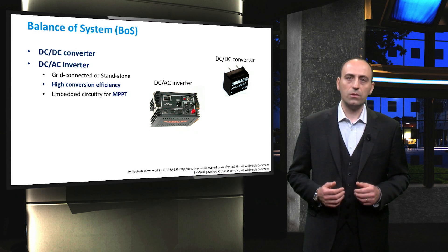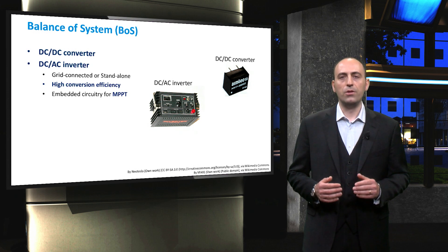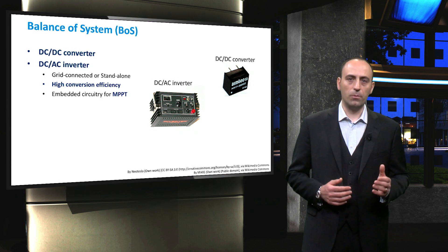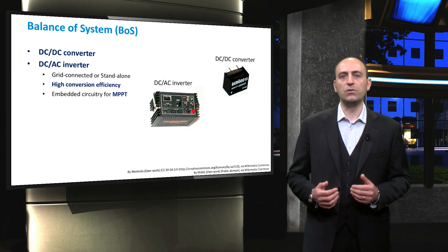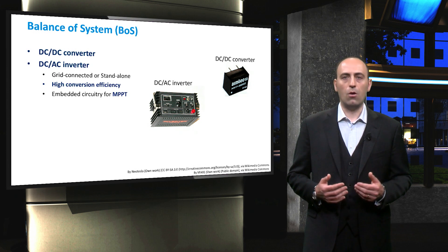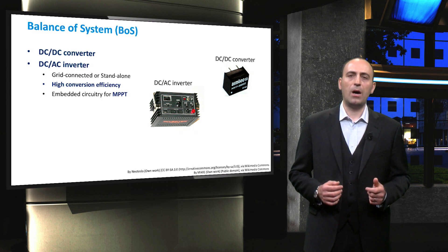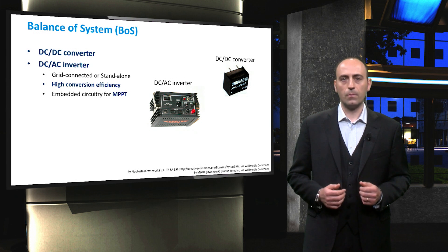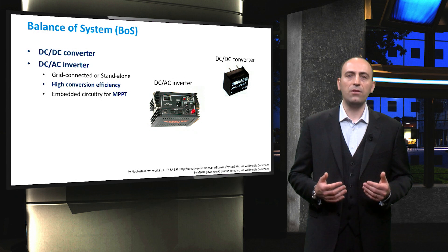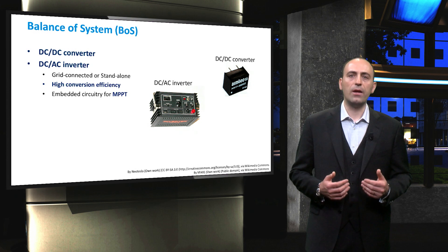DC-AC converters, also known as inverters, are used in grid-connected systems. The inverters convert the DC electricity coming from the PV modules into a sinusoidal AC electricity form that can be fed into the grid after supplying the loads. Of course, we also have standalone inverters that change the PV power coming from the module to AC power delivered to a certain load. Both types of inverters are characterized by high conversion efficiencies between 94 and 98 percent, depending on the working conditions and their embodiments.